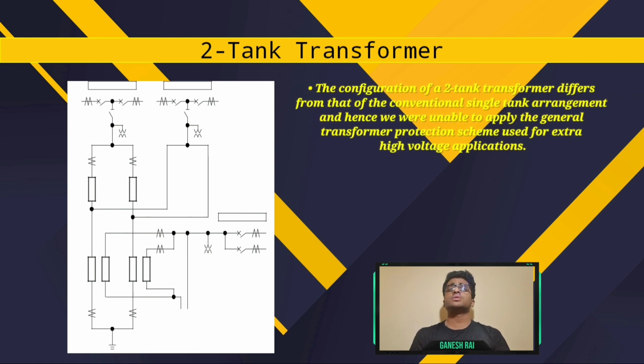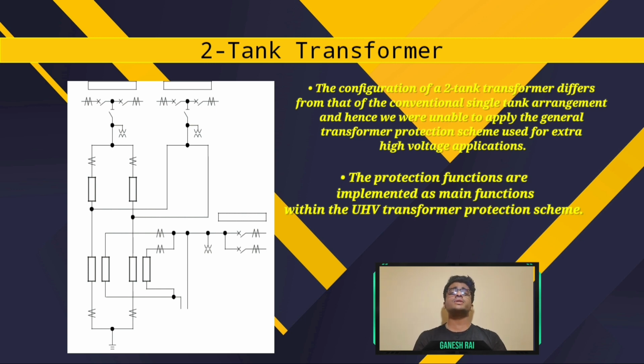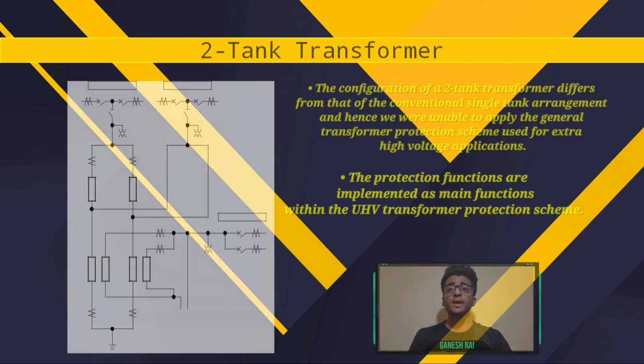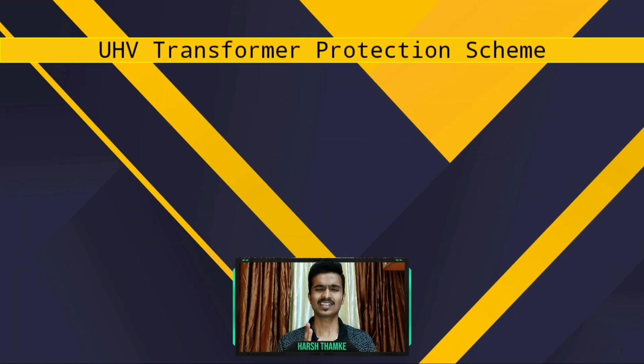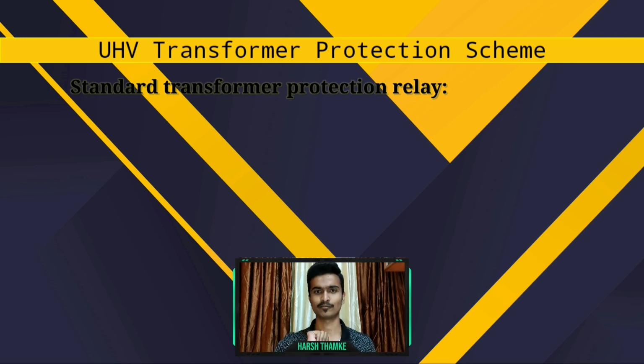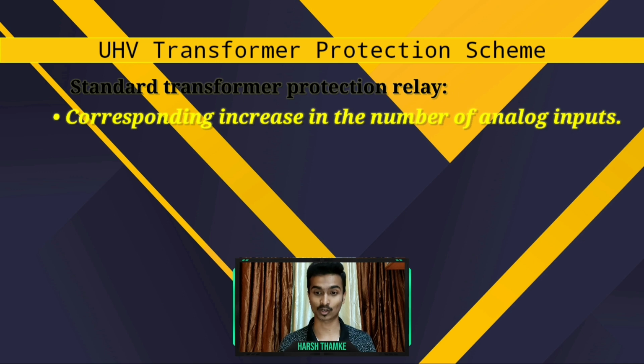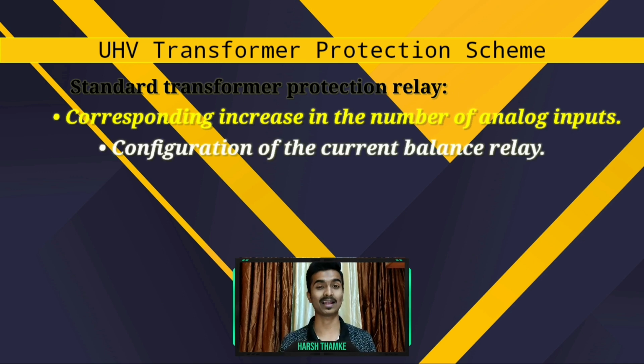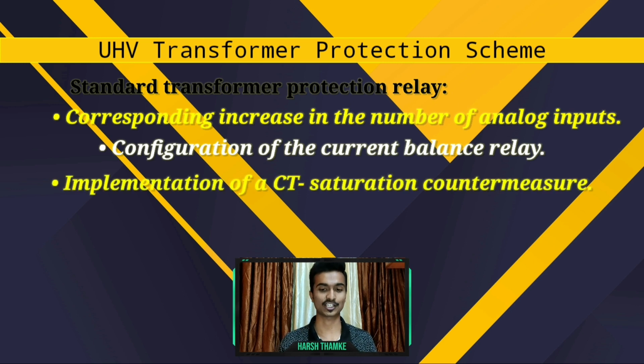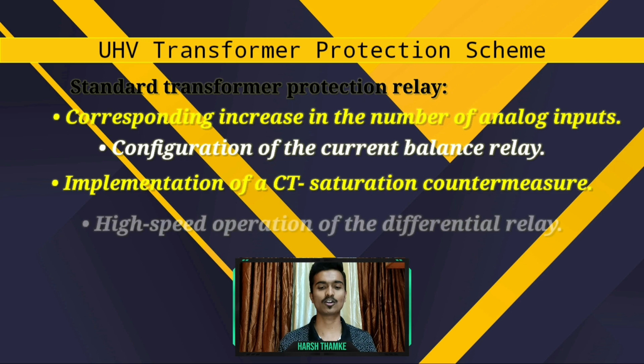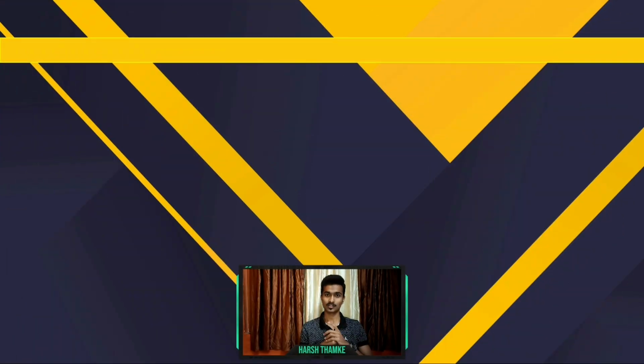The configuration of a two-tank transformer generally differs from that of the conventional single-tank arrangement, and hence it is impossible to apply the general transformer protection scheme used for extra high voltage applications. The protection functions are implemented as main functions within the UHV transformer protection scheme. Standard transformer protection relay is done in four methods. First, corresponding increase in number of analog inputs, configuration of the current balance relay, implementation of CT saturation countermeasure, high speed operation of differential relay. Let me tell you the first method.